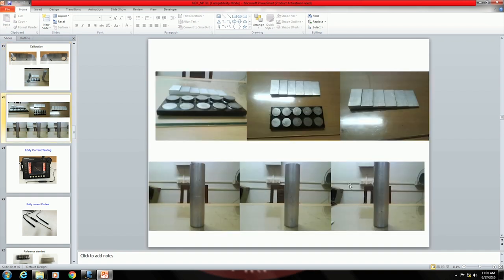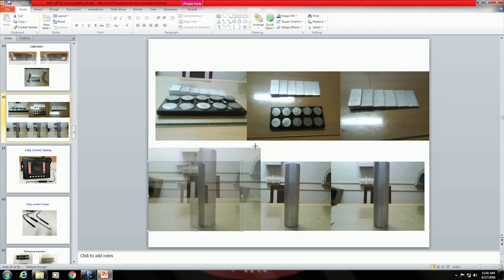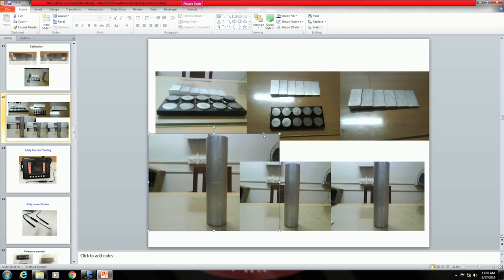Okay, so these are the different types of calibration blocks, as you could see. For example, you could use a cylinder like this, and if you take a close look, let me magnify this, let me increase the size. Okay, so I do not know whether on the screen you could see around this area there is a small hole. Okay. So this hole is at a distance from the top which is 50 millimeter. So this is at a known distance, as I told. So using this, you could get an echo and then see whether it is coming at that particular distance, or that time corresponding to this distance. Okay. On the time base, you can see that.